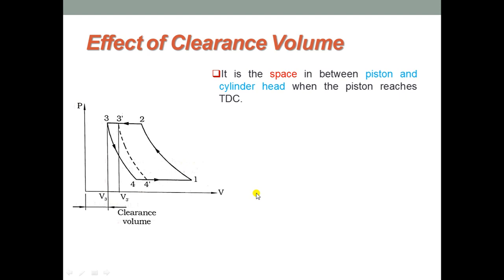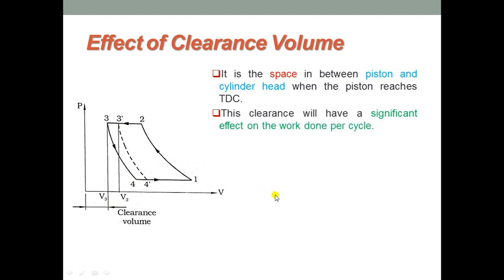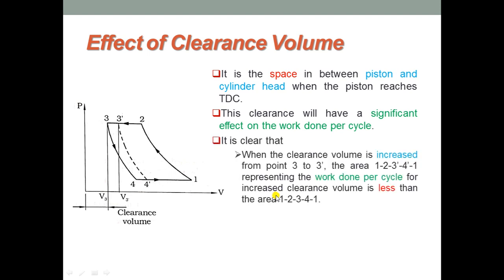This clearance has a significant effect on work done per cycle, as illustrated in the P-V diagram. When the clearance volume is increased from point 3 to point 3 dash — that is, the volume increases from V3 to V3 dash — the area representing cycle 1-2-3dash-4dash-1, which is the work done per cycle for the increased clearance volume, is less than the area 1-2-3-4-1. Thus, an increase in clearance volume causes a decrease in work done per cycle.